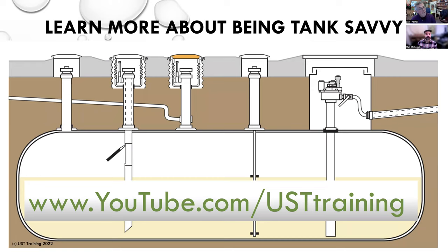Bill Combs did ask about wireless electronic line leak detectors. For a while, there were electronic line leak detectors that didn't have a direct power line going to them. They used a wireless signal. They're not really popular anymore. It turns out the signal from the fluorescent lights of the canopy was interrupting the signal, and so the signal degradation was serious. So if you ever see a WPLLD, a wireless pressurized line leak detector test, it probably ought to be replaced with a more contemporary one.